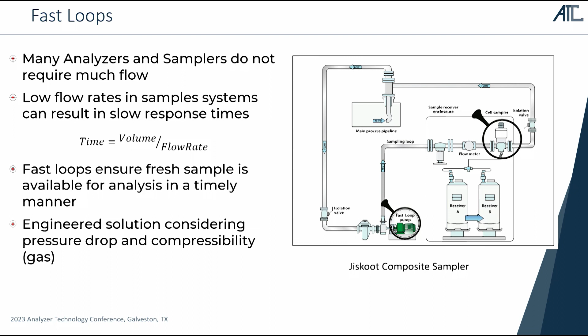Fast loops help ensure we get a fresh sample over to where we're going to do our measurement, and they often have to be engineered properly. If it's liquids, we often have to worry about pressure drops. If it's gases, we have to worry about compressibility. There's a lot of factors that come into play when we're trying to figure out how we're going to design a fast loop for, say, a sampler.